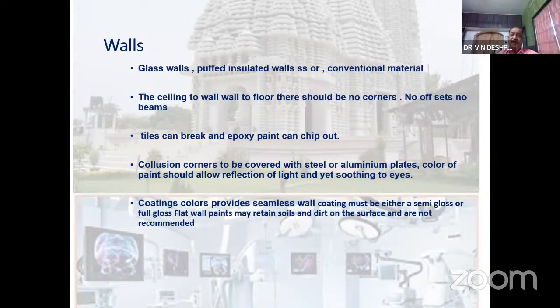The tiles can break and epoxy paint can chip off. Collision corners should be covered with steel or aluminum corners and plates, because if the stretcher hits against the wall, it creates a rough surface, which is bad for cleaning and creates a dust lodging area in the operation theater.